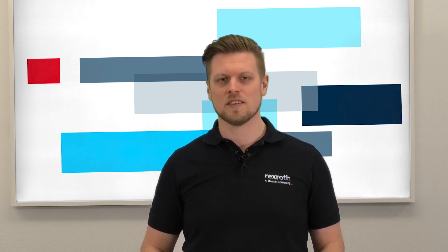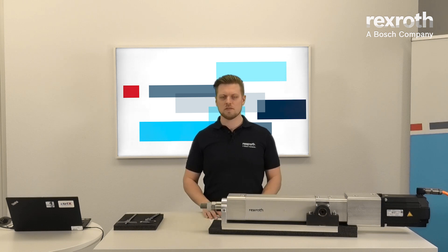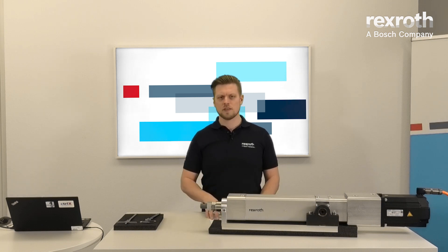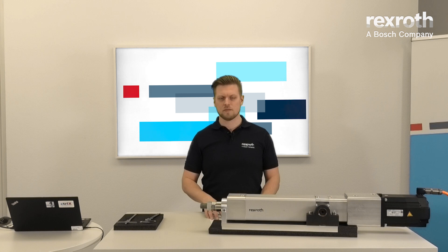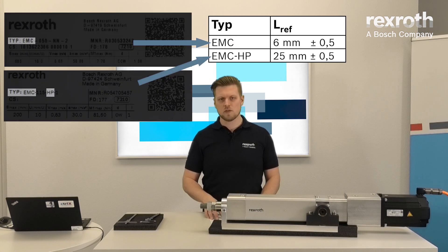Today I want to show you how to find and set the zero point of a Bosch Rexroth EMC or EMC-HP electric actuator. The zero point equals the position of the actuator when the piston rod is moved to the reference measure LREF. You can find the exact value for LREF in the documentation.